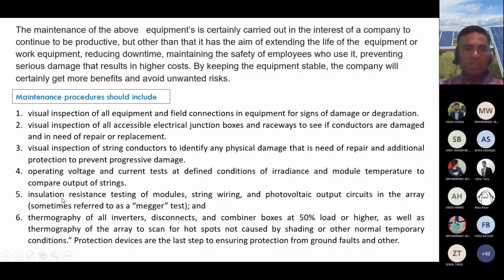And this is also number 5. We do insulation resistance testing of the module. Especially for this testing, we do it during the regular maintenance, like once a month. We need to do the insulation resistance test after the visual inspection, when we think that a string looks like it has an issue. Then we need to do the insulation resistance test to make sure the cable is still good.